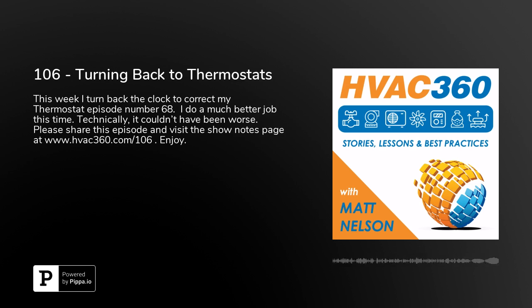I guess most people have a programmable thermostat of some variety in their home. And that you can actually select. That's going to be a low voltage. So you have your transformer, a little transformer that's located down in the unit, the furnace or your air handling unit. And it's going to send up the wiring. You're going to have low voltage wiring going to the back of your thermostat, and you're going to select whether you want a heating mode, a cooling mode, or auto, which can select either or, but you're going to have basically a set point that you set, and depending on heating and cooling, when it's above or below, it'll actuate accordingly. So I guess that's the third type, what I'm referring to as an intelligent, self-contained, user-selected mode.